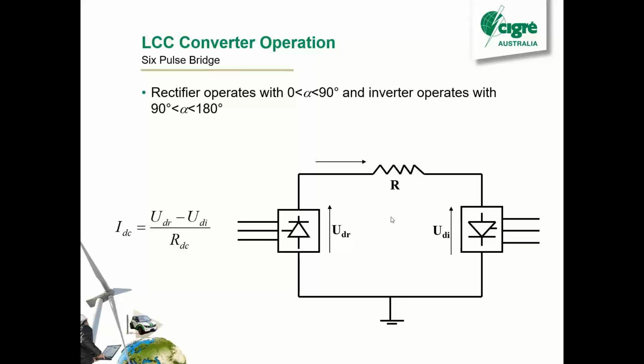So the way we do it, we fire the rectifier with the alpha between 0 and 90. I was telling you about the rectifier before. At the inverter, you wait later, you fire that at 90 and 180. So that's actually on the negative side. On the inverter, you actually get a negative voltage compared with the rectifier.